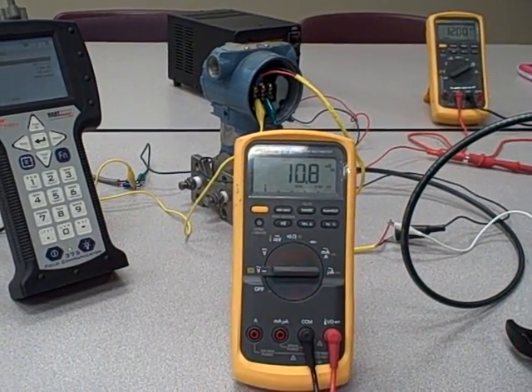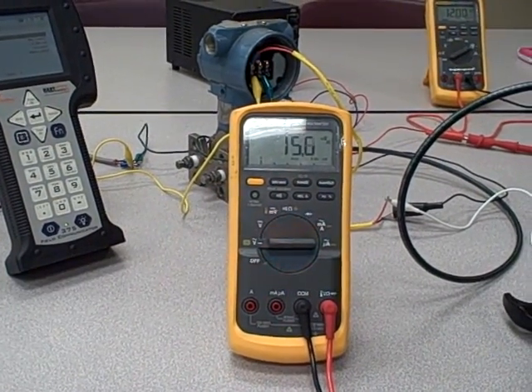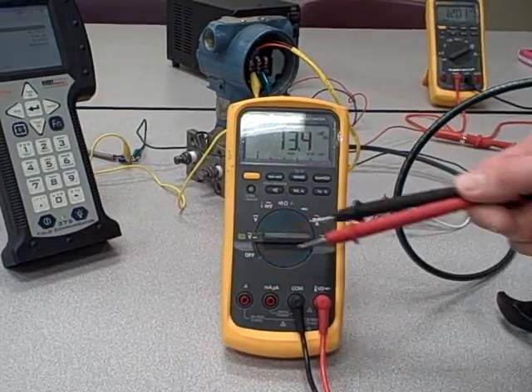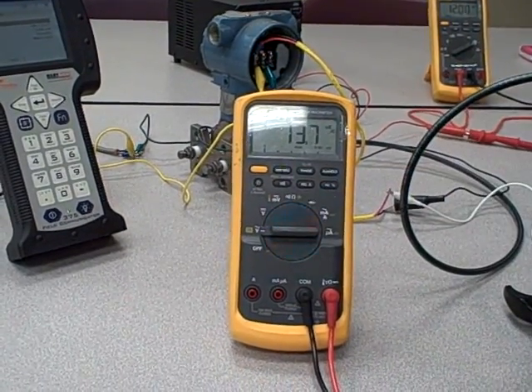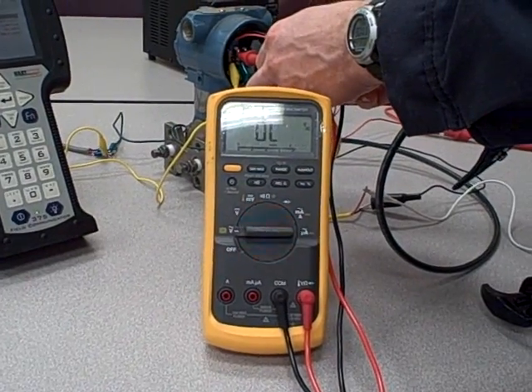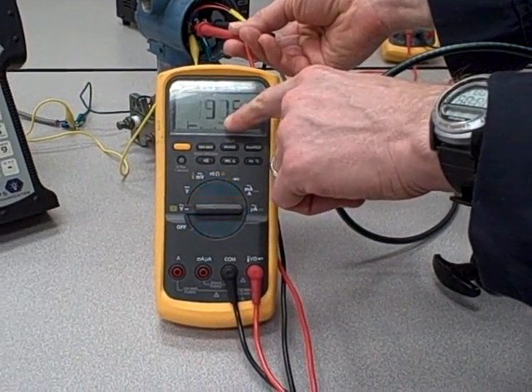This is another Fluke Model 87-V meter. These Fluke meters do a great job of distinguishing between AC and DC signals. So I'm going to set it on AC, and when I attach the meter leads to the two terminals on the transmitter, we're going to notice about 100 millivolts worth of AC communication.